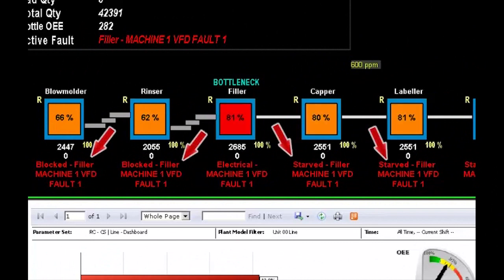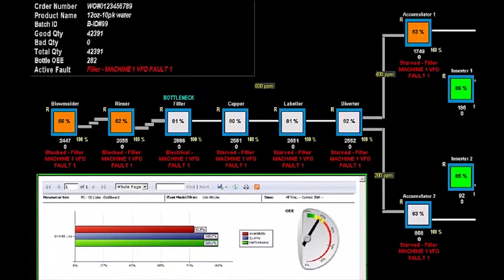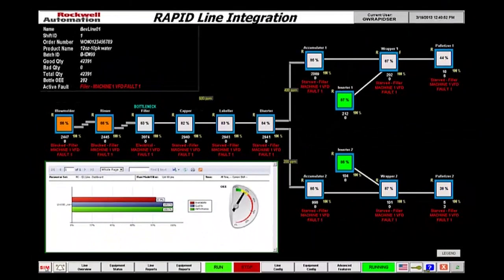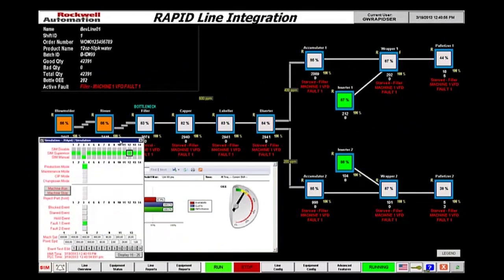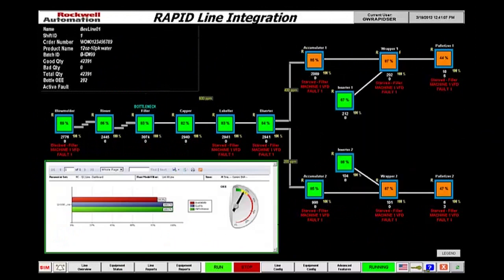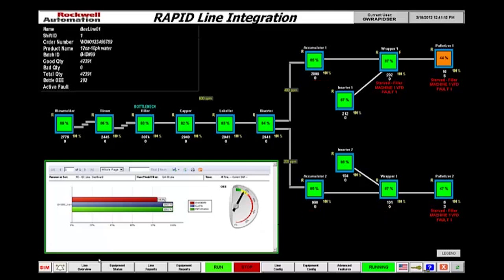As you can see, the bottleneck machine — the filler — went down for a fault. Associated timers built into the recipe-based configuration for RAPID sent suspend signals for blocked and starved states. So the machines do not necessarily need to see each other or know the status of each other; rather, the RAPID Supervisor controls them. The filler is faulted, and up and downstream from there the root cause of the other faults and blocked and starved conditions is also shown. Throughout the entire line, the cascade control blocked and starved all the machines. Now I've restarted the filler, which will do the inverse — unsuspending all machines from a line supervisory state — and the individual machines are going back to a running state.